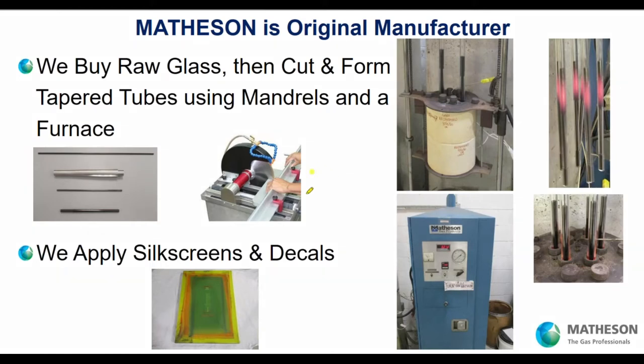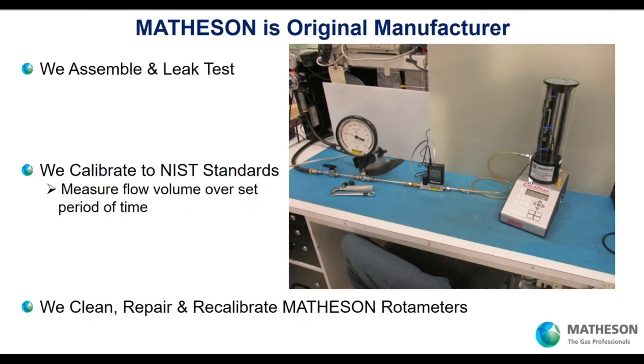We form the tubes around mandrels. Here are four examples of mandrels, and we choose the mandrel that goes with the rotameter we're going to manufacture. That mandrel with the glass tube is put into a furnace. Here's our furnace and pictures of the tubes around the mandrels in the furnace. After the tube is created, we apply the silk screens and decals to our rotometers. We assemble and leak test them, then calibrate to NIST standards.